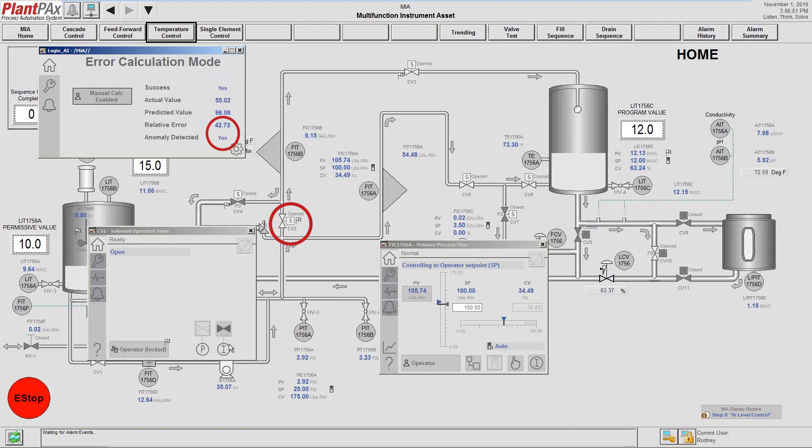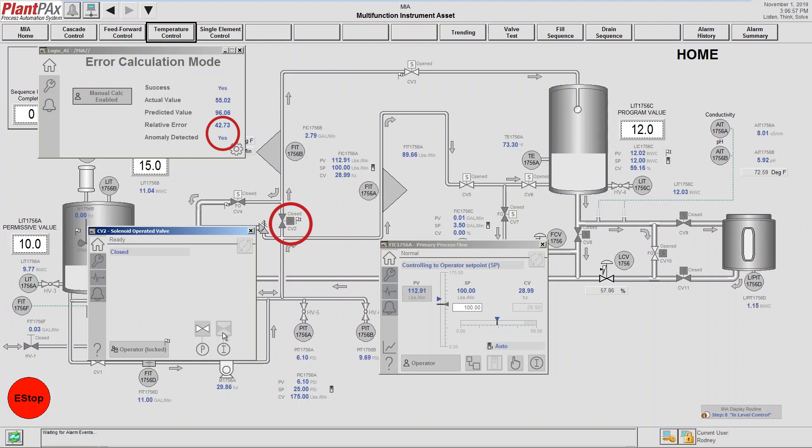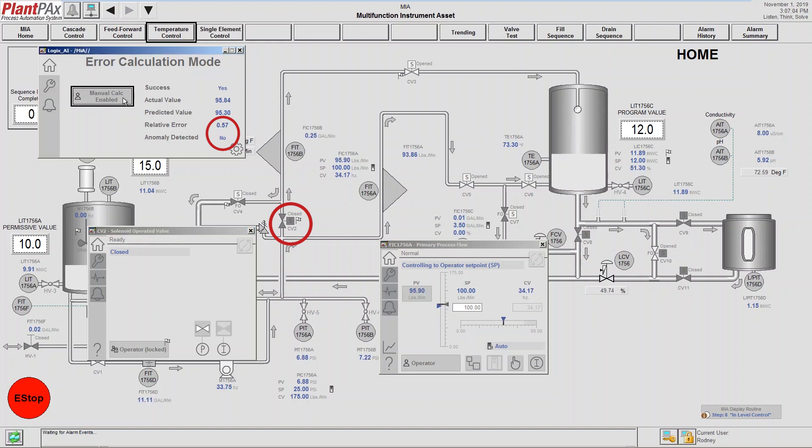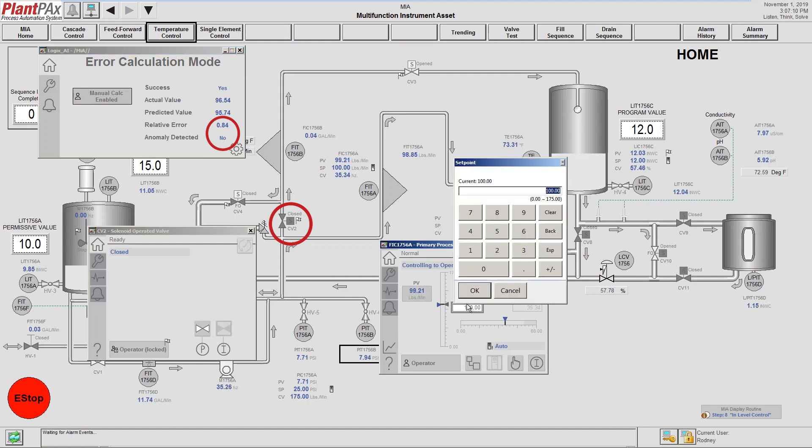We're going to close the valve, allow the system to stabilize a bit, and then we're going to do another manual calculation enable, and our anomaly should disappear. And you can see that it does. So we're back to that steady state model. So the model has now verified that we do not have an anomaly.